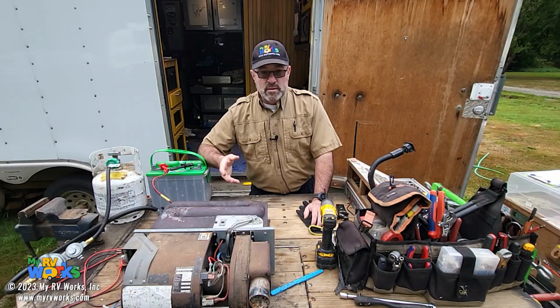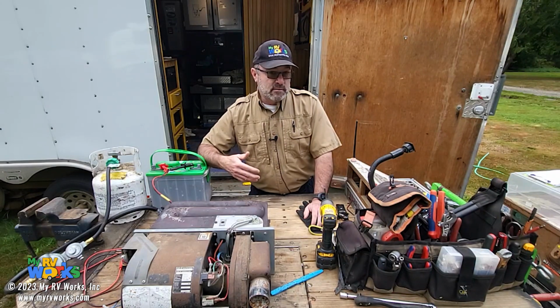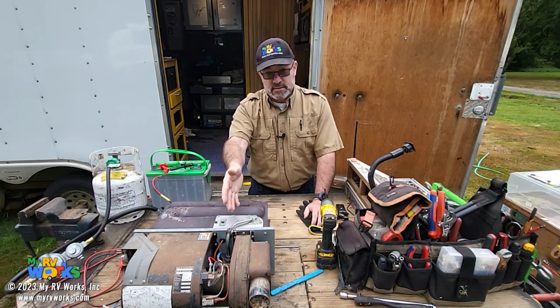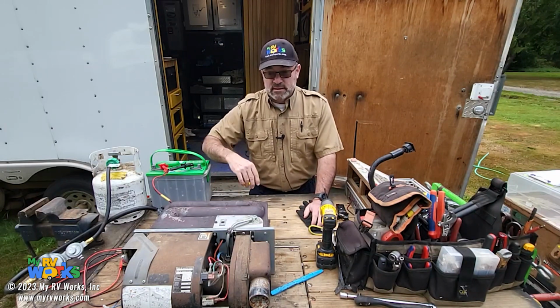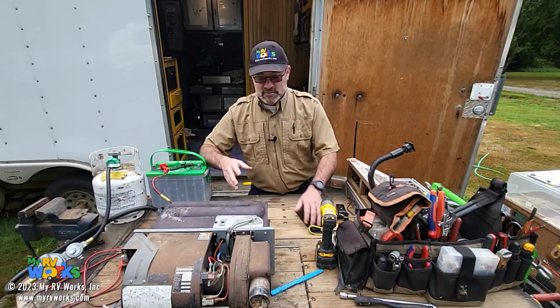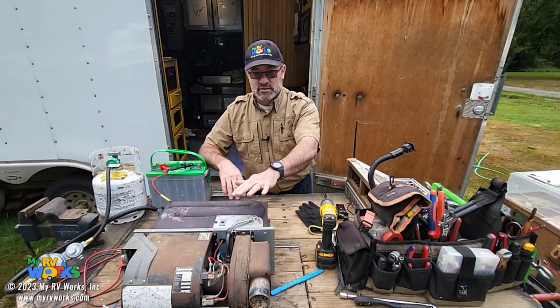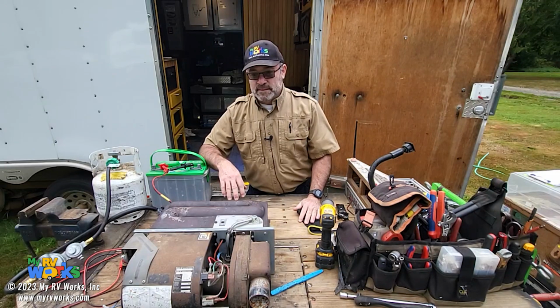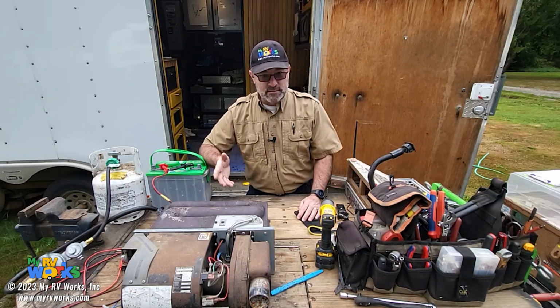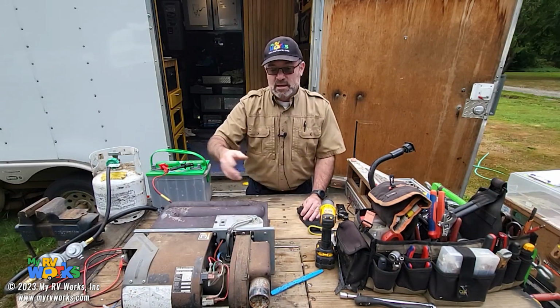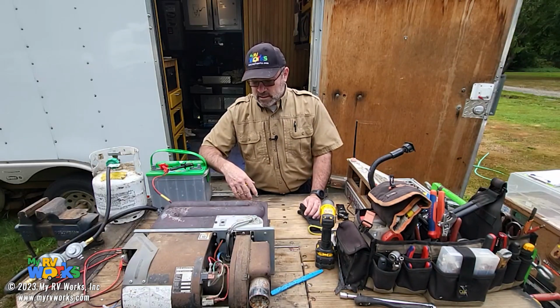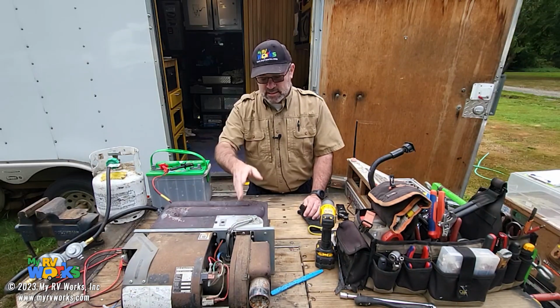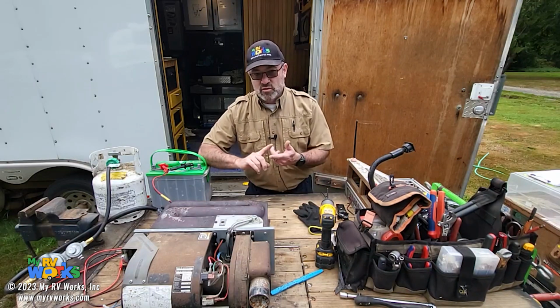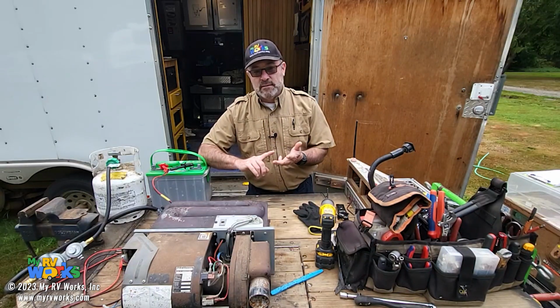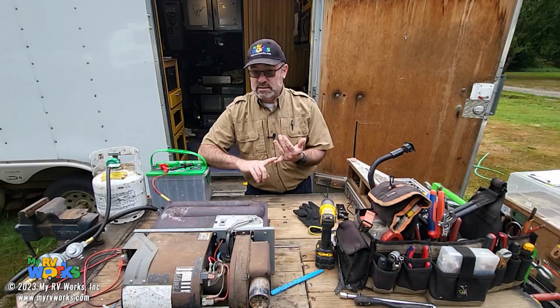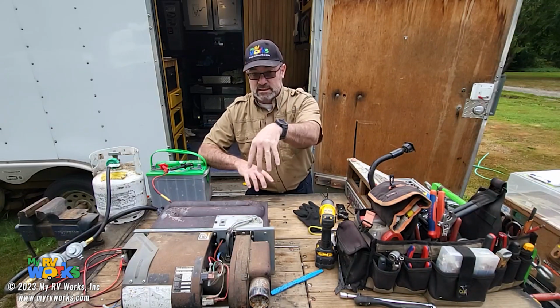Another instance where you may not detect flame is if you run out of propane. Certainly if you run out of propane, your flame has extinguished, and the control board at that point says, I see no flame. Even though everything's perfectly dialed in and you've got a perfect furnace, if you run out of propane, the control board cannot detect the flame because there is no flame, and the control board will then shut off the gas valve. So the first issue is it cannot detect flame: the control board, electrode wire, electrode gap, or the electrode itself. We're going to get into all that when we get inside the furnace.